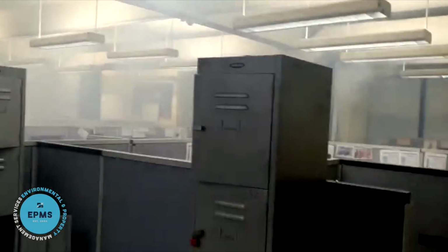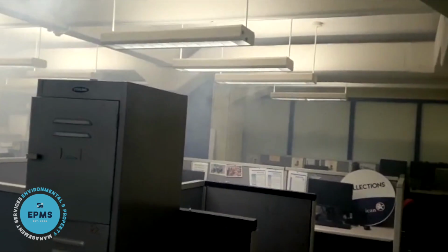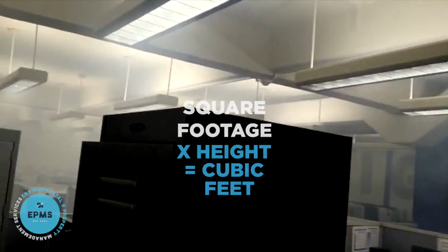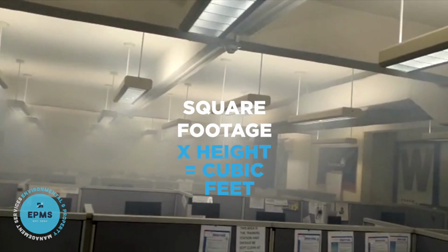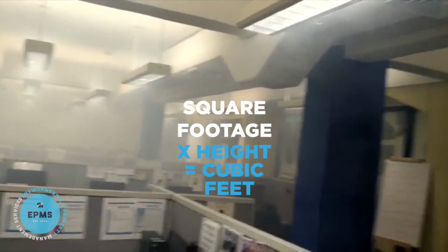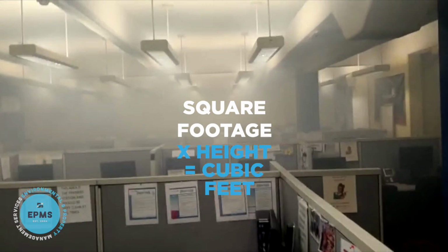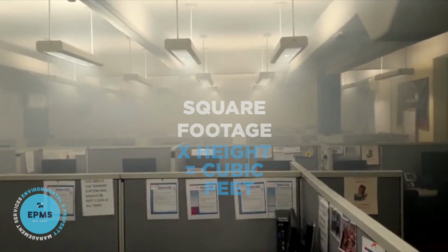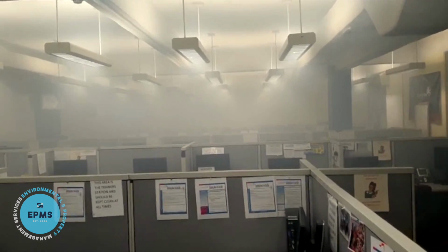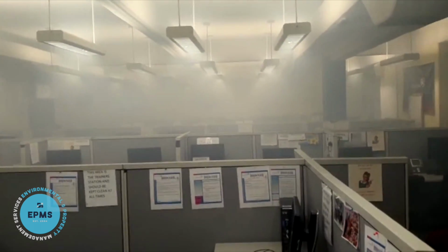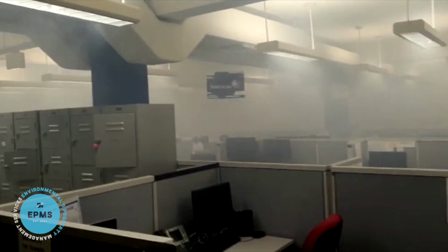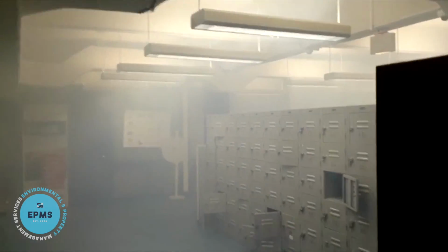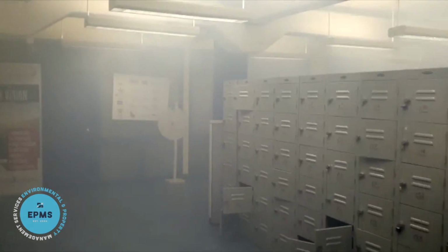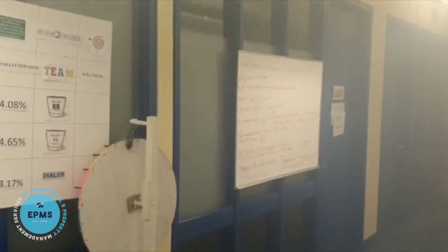Now, in order to reach that 100% saturation point, what we do is we calculate the square footage of the room. So if the room is 100 by 10, that's 1,000 square feet. And then we multiply that by the height of the room, which is another 10. So we end up with 10,000 cubic feet. So we set our equipment to 10,000 cubic feet and calculate the amount of time that we need to run and reach our saturation point. And once that calculation has been done, the equipment will run until we reach that saturation point.